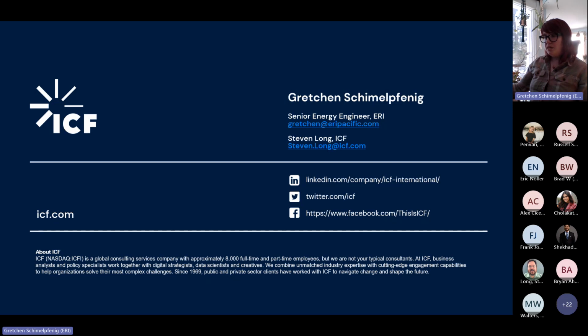The low mass boiler is priced on square footage, including distribution equipment, for a new build. For a retrofit project, the higher cost of a low mass boiler compared to a unit heater would likely be smaller if they didn't need large infrastructure improvements. Overall, the 75 to 88% higher cost quoted in this presentation is based off the boiler alone, so this is something to consider.